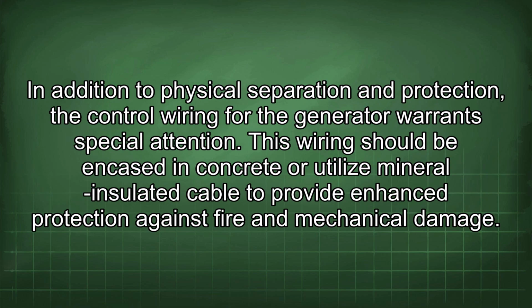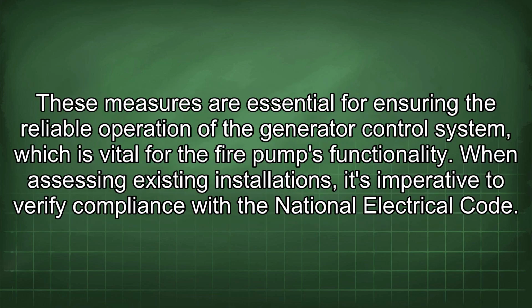In addition to physical separation and protection, the control wiring for the generator warrants special attention. This wiring should be encased in concrete or utilize mineral insulated cable to provide enhanced protection against fire and mechanical damage. These measures are essential for ensuring the reliable operation of the generator control system, which is vital for the fire pump's functionality. When assessing existing installations, it's imperative to verify compliance with the National Electrical Code.